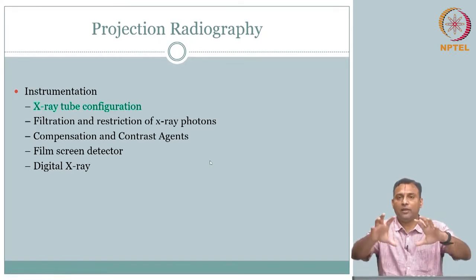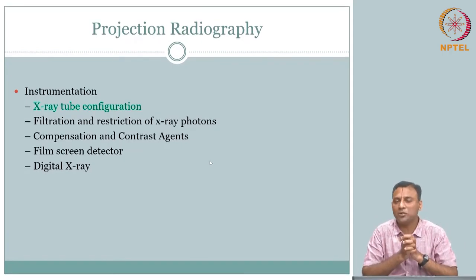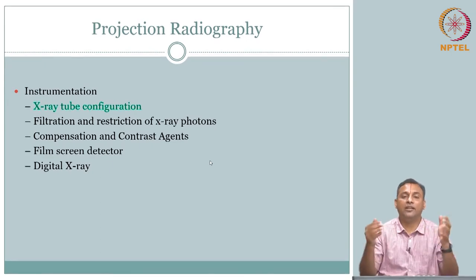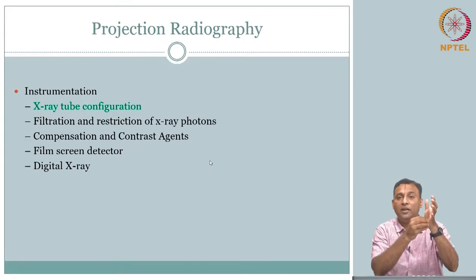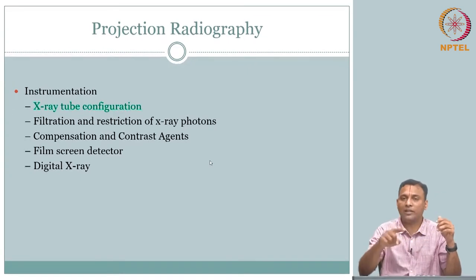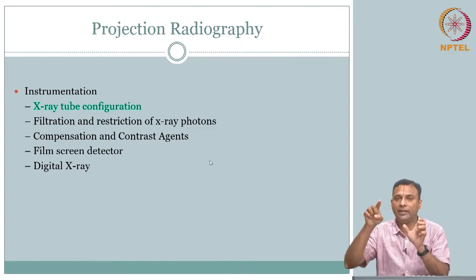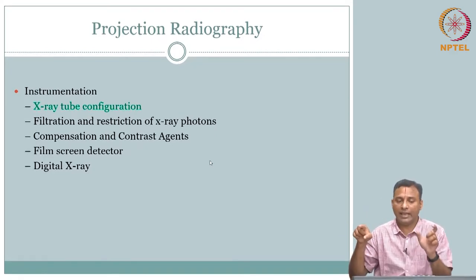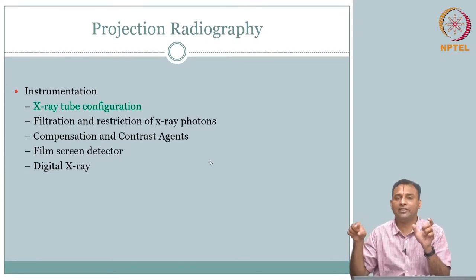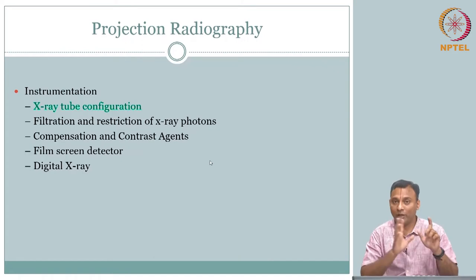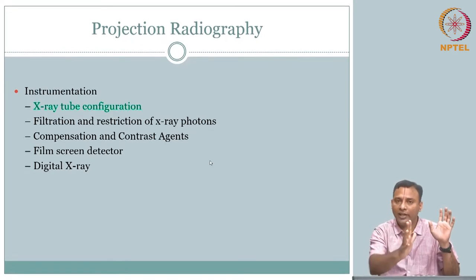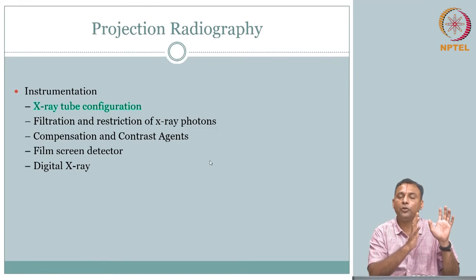We have created the x-ray. What is coming out from the anode is a polyenergetic x-ray spectrum — a hill-shaped curve due to Bremsstrahlung, where photon count rises then drops, with the maximum energy corresponding to the applied kVp. Now the question is: do we want to send that spectrum directly to the patient, or is there physics we need to pay attention to? This is where filtration comes in.